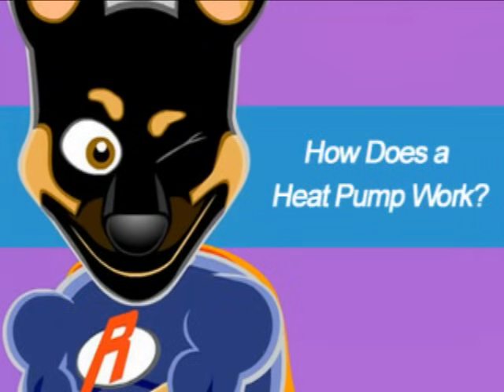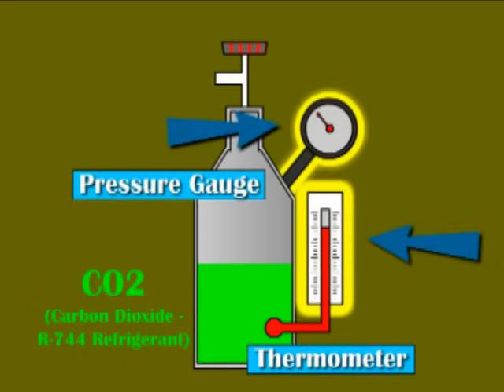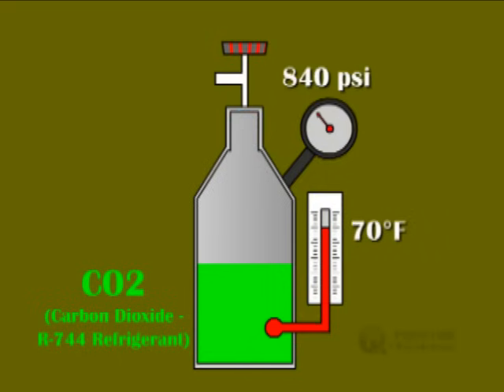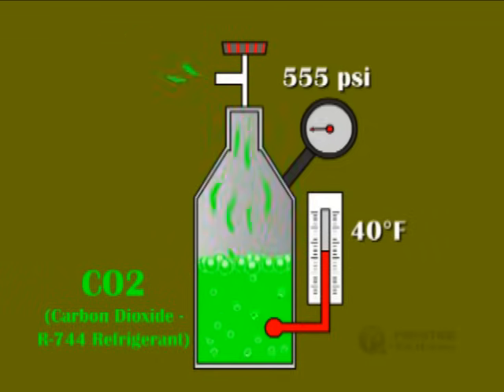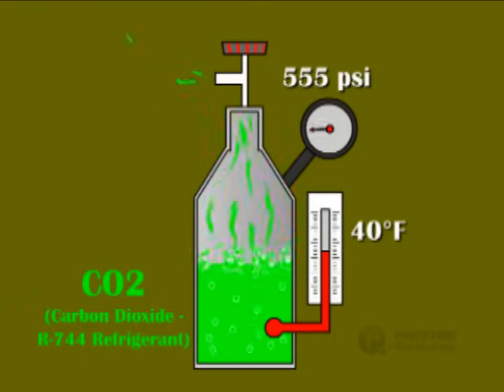How does a heat pump work? All air conditioning systems, including heat pumps, rely on the refrigerant's pressure-temperature relationship. When a refrigerant evaporates, or boils, it absorbs heat at a very high rate, as is the case with all liquefied gases. Since refrigerant has a lower boiling point than most liquids, we can easily manipulate it so that the only heat source needed is room temperature air.